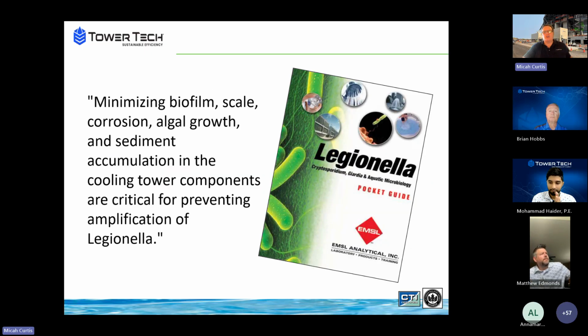So looking at the pictures we shared earlier of the nasty cooling tower basin, I think it's pretty obvious to everybody that algae is one of the primary food sources for Legionella bacteria to grow. It's actually their number 1 food source. But there are actually number 2 and number 3 food sources that feed and breed Legionella bacteria. Brian, let's talk about what those are in cooling towers. The EMSL Pocket Guide addresses those. What are they besides algae? Besides algae, the Pocket Guide looks at biofilm that happens in the towers, and scale, which is something you can greatly affect, that can be minimized or even eliminated in some cooling towers.